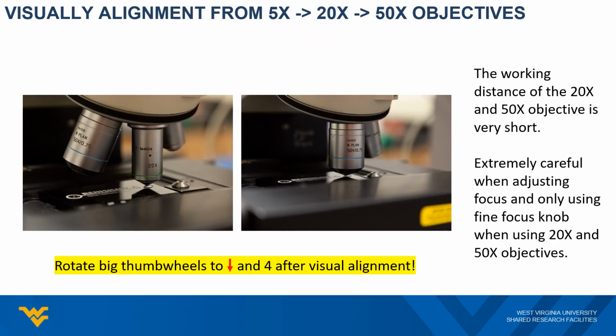When using the 20 times or 50 times objectives, the distance from the sample surface to objective is less than 1 millimeter. So you need to be extremely careful when adjusting the focus and should only use the fine focus knob to get the proper focus. Once you got the desired image, move the region of interest to the center of the crosshair, then rotate the big thumb wheel to down arrow and 4 position. Now we're ready for Raman measurement.